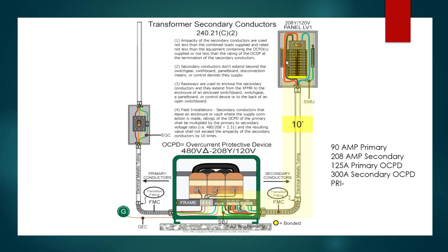240.21(C)(2). Now let's do some assumptions here. What if we said the load was under 200 amps, and so the engineer sized this at 200 amp? We don't know what the transformer's kVA rating is yet because the engineer's sizing it all. But in this case, this is a 200 amp rated device right here, and the load was less than 200 amps for whatever reason, 200 amps of non-continuous. So he's done this, and this is our load. Okay, let's just take it at that. These conductors are sized based on the 200 amp device, and we're going to see that right here in a minute. So these are 3/0 and they're good for 200 amps. That's based on the engineering design.